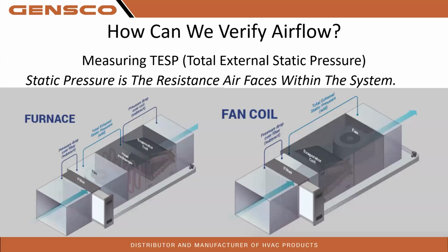I've seen systems where the filter alone was causing more resistance than the entire ducting system. So if you need to take a picture of this screen right here, right now, please do so. I'm going to give you another few seconds to take a picture. But this is very important on how to understand taking this.